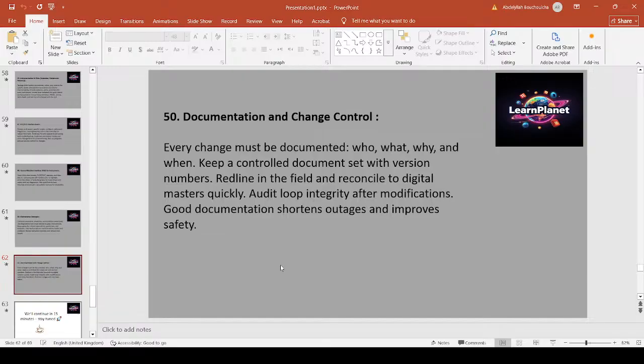Documentation and change control. Every change must be documented: who, what, why, and when. Keep a control document set with version number. Redline in the field and reconcile to digital masters quickly. Audit loop integrity after modification. Good documentation shortens outages and improves safety.